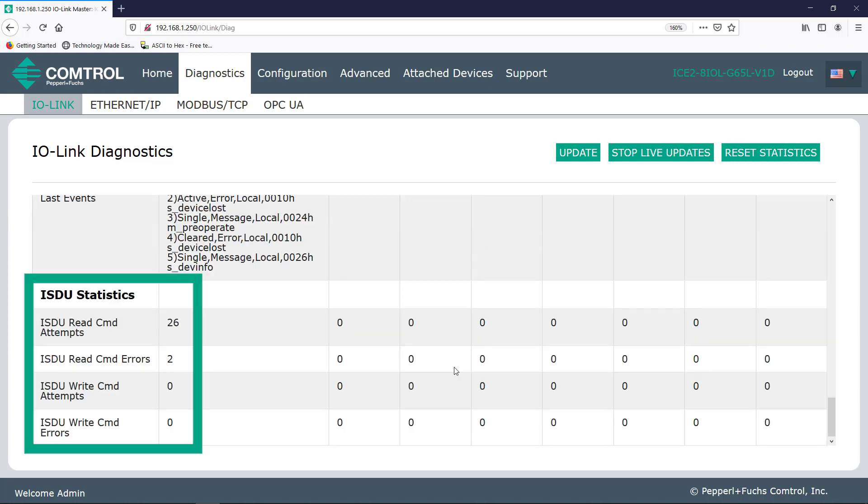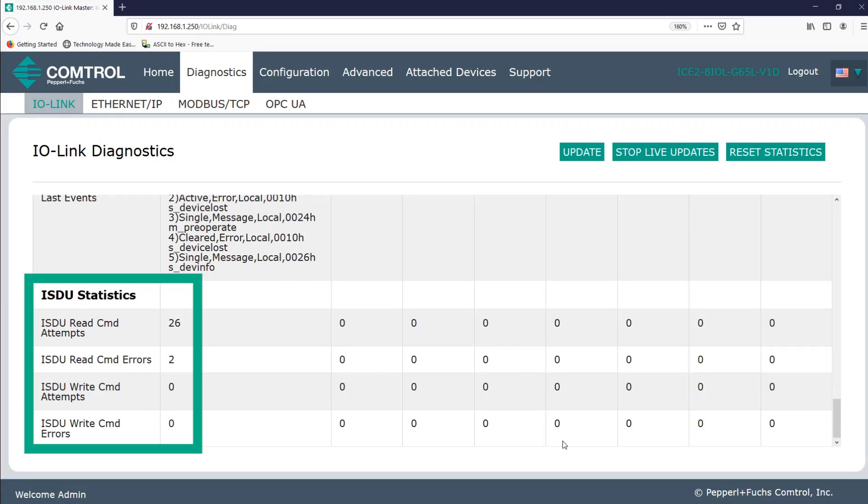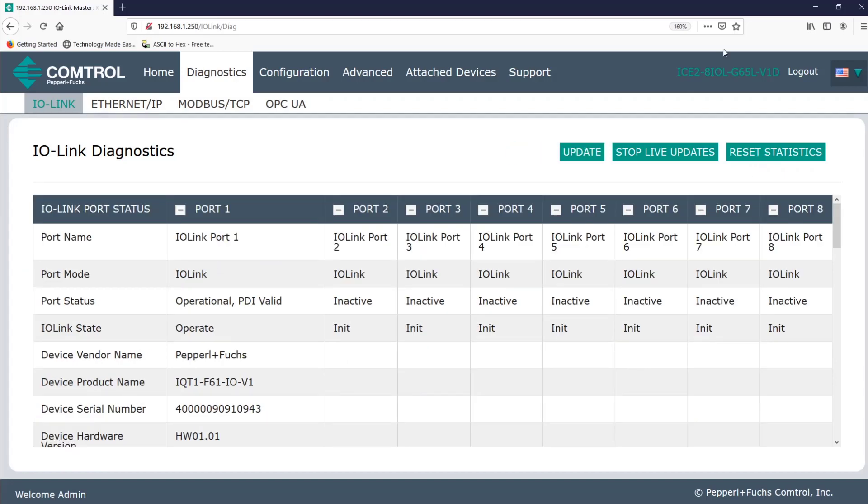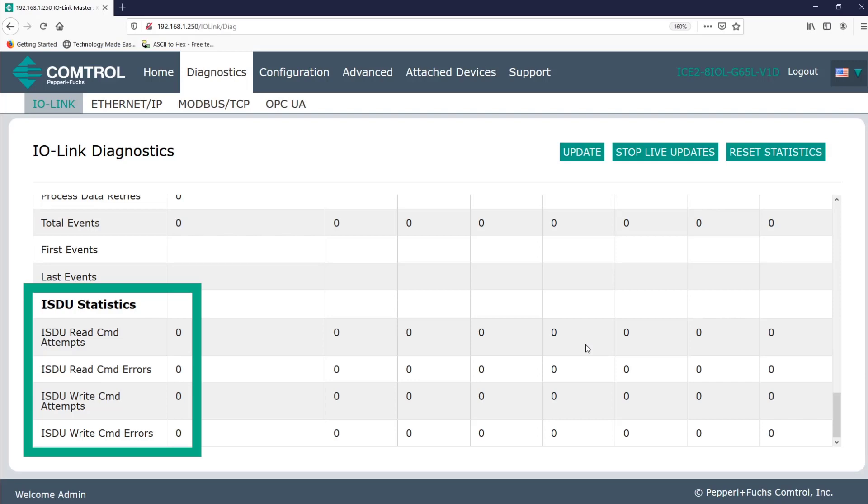So now let's look at the ISDU statistics section. Now, when you're actually setting up your device, you'll probably not only see some events that trigger as mentioned above, but you'll probably also see some ISDU statistics jump up as well. And after the sensor is connected, I recommend clicking on the reset statistics button that's shown at the top. This will help clear out events and stats that were triggered by the setup. Now, a real quick note on ISDU statistics. Don't be surprised if over time you see some of these increase slightly. There are background processes going on which act like a heartbeat validating certain parts of the device. They'll increase too when you initiate ISDU commands, which I'll talk about in a later video.